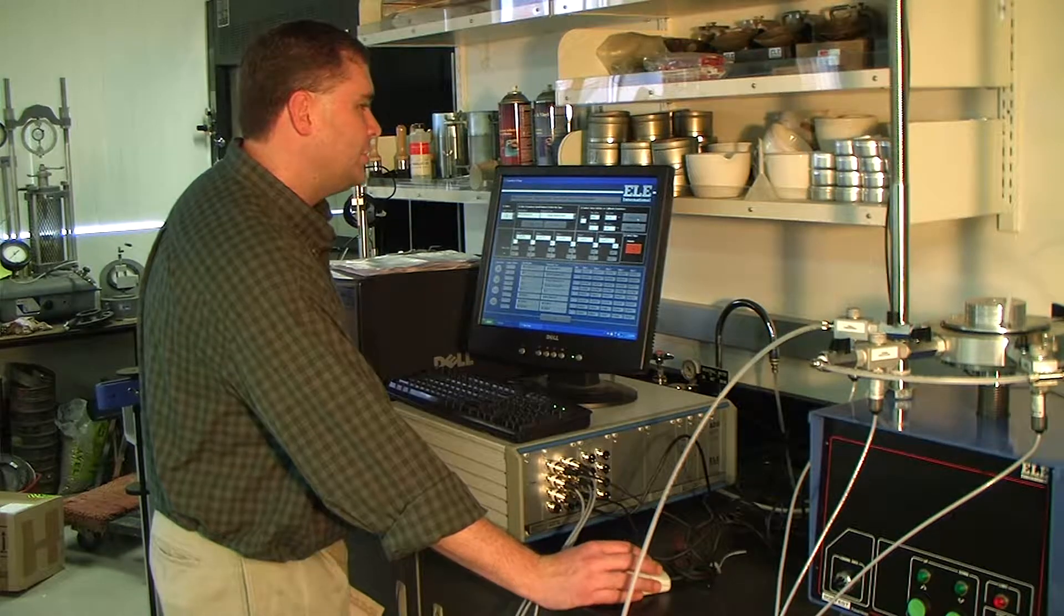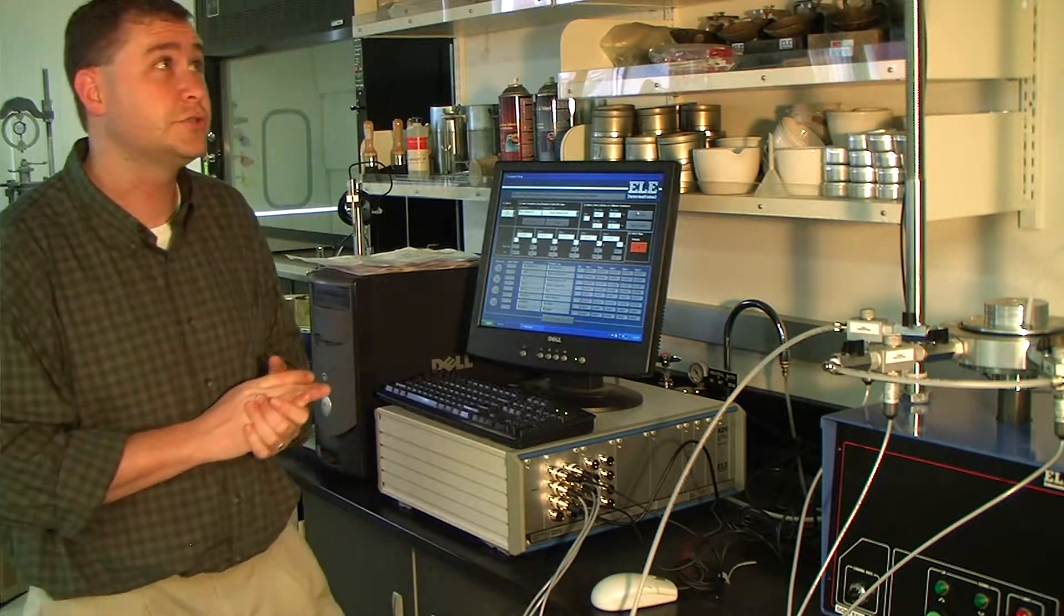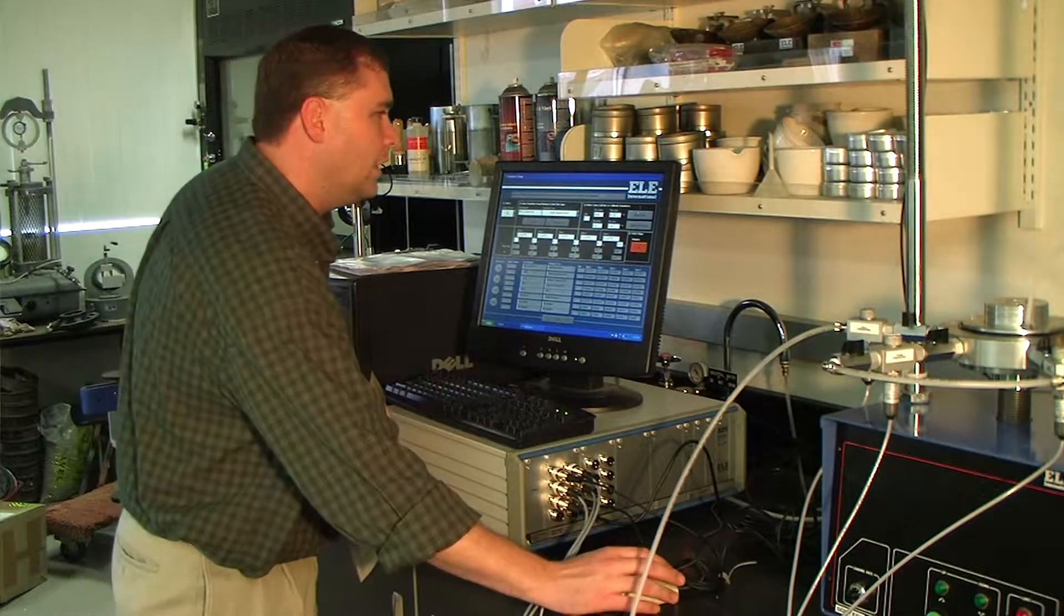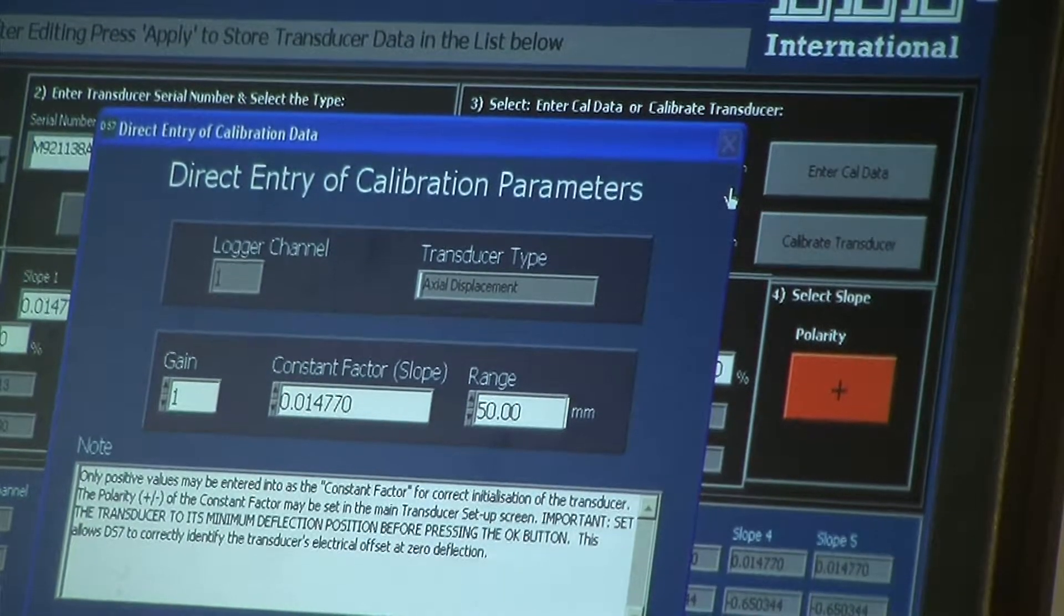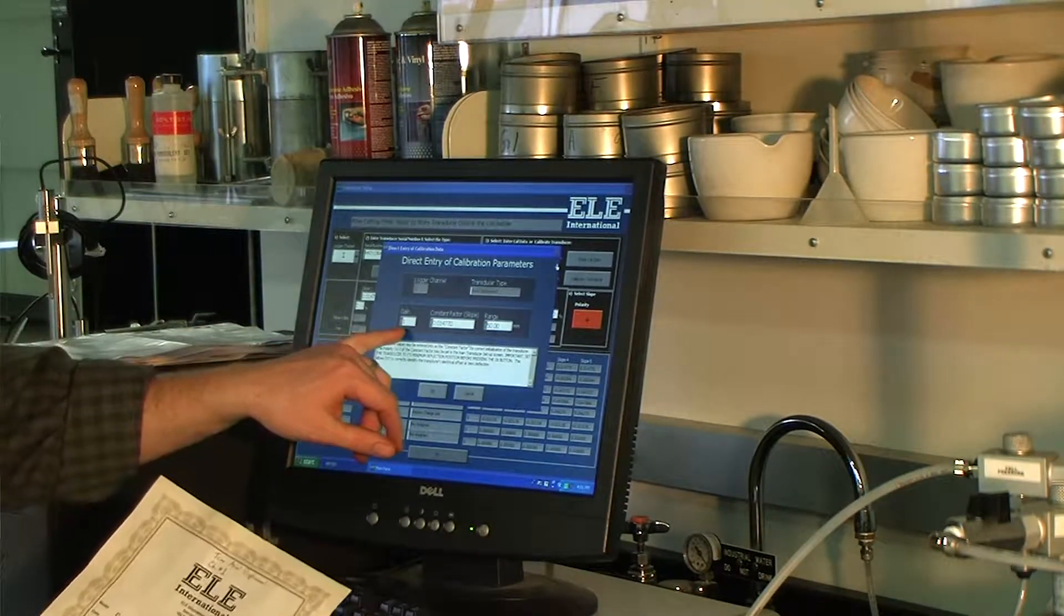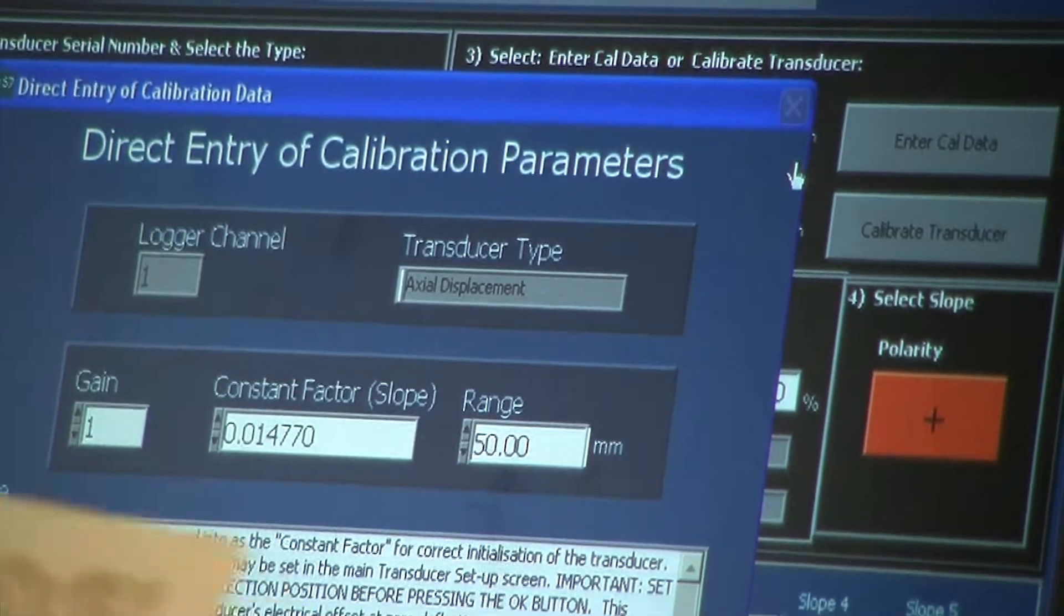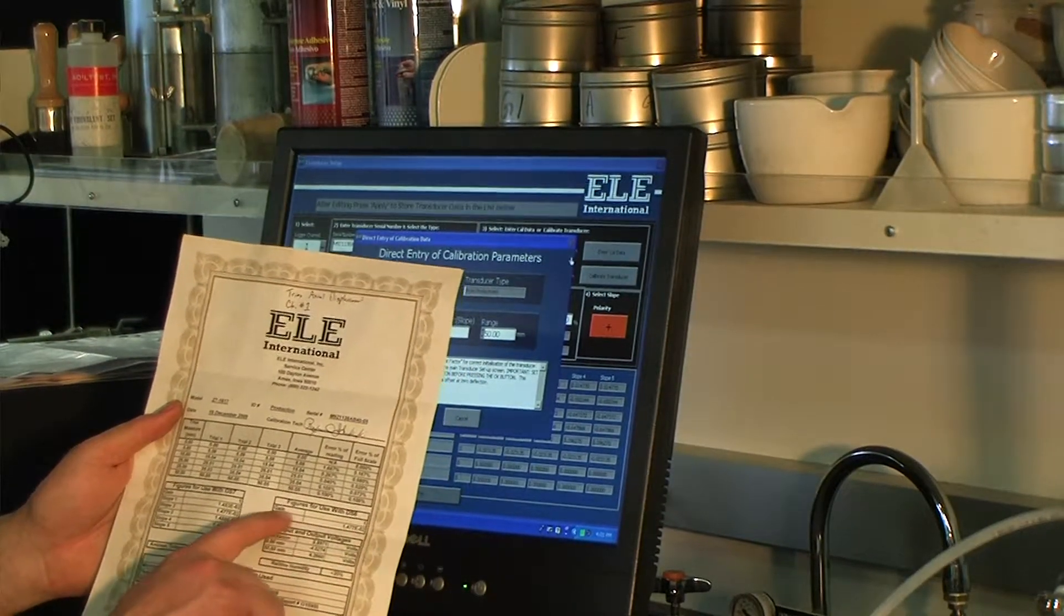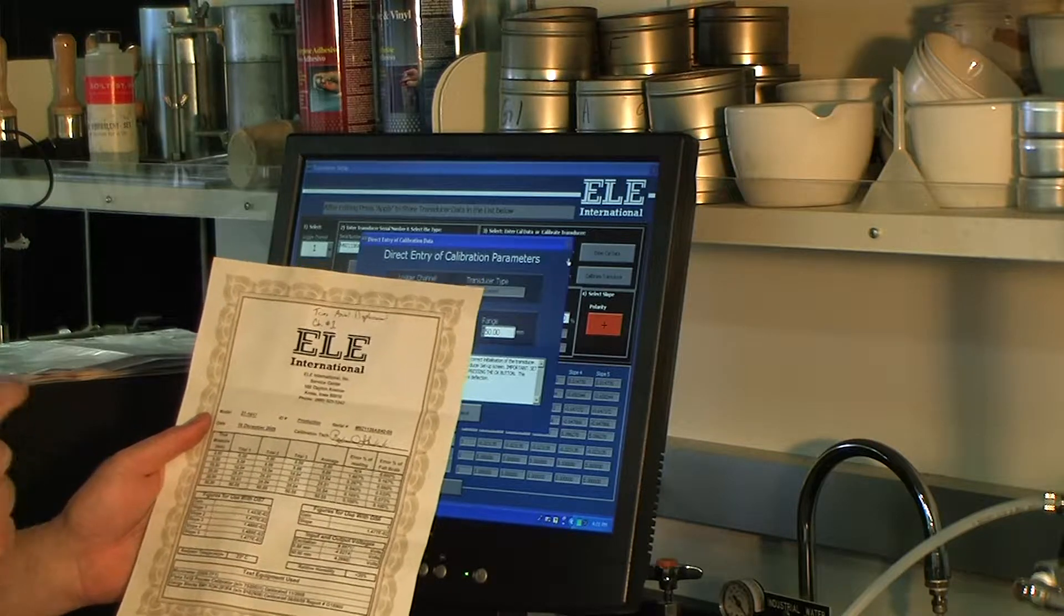This one we have already talked about is the axial displacement. And then we go to step three, which is where we actually enter or calibrate the transducer itself. We have that option. Because these transducers are new out of the box, they have been calibrated at the factory and are provided with calibration sheets, which I have already shown you. So we will hit the button called enter cal data. It will bring up a new screen where we need three pieces of information, all provided on this calibration sheet.